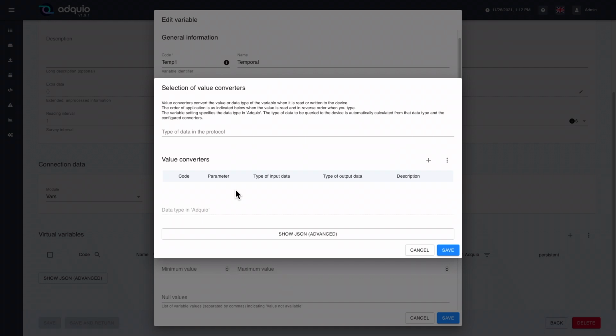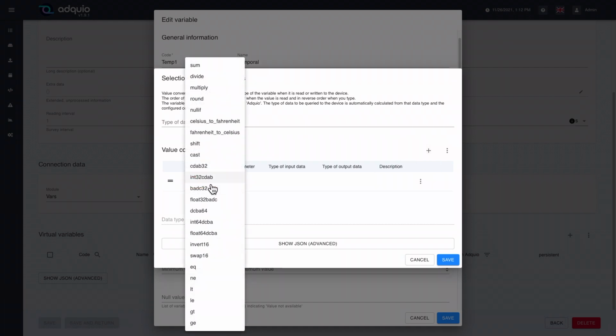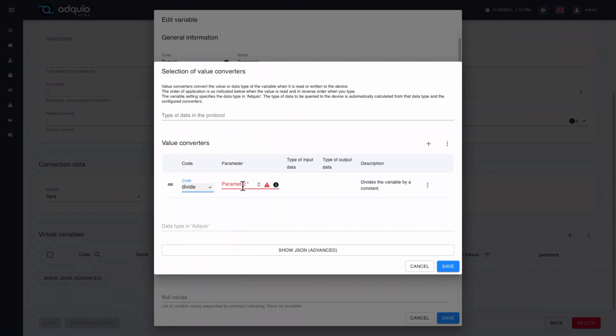This means that, if for example, we have a device, which is usually the usual in Modbus, which gives me a temperature, but, gives me multiplied by 100, or, by 1000, here, I will have the possibility to tell it, that I want to divide it by 100, because, that Modbus device works only with integers, so, to send me 22 degrees, it sends me 2200, so, with this, I already get that the variable that came from a Modbus device multiplied by 100, when dividing it by 100, we convert it into a value of already usual work.